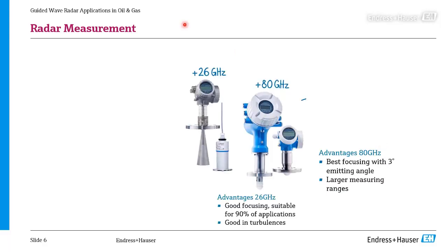So the higher the frequency, the smaller is my beam angle. And if I have a smaller beam angle, I will not touch obstacles in a tank, for example. So this makes my life easier. It makes it easier to commission, for example. And since the focus is smaller, I can also typically go to larger measuring ranges because I have a better focus, you could call it. But still, there are other measuring technologies, other frequencies.